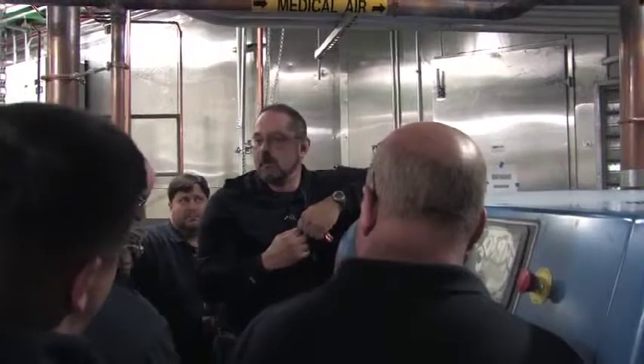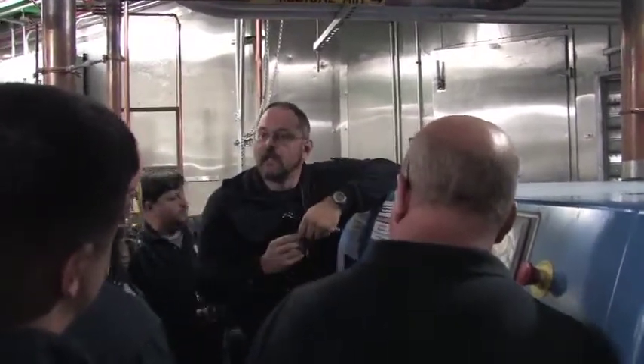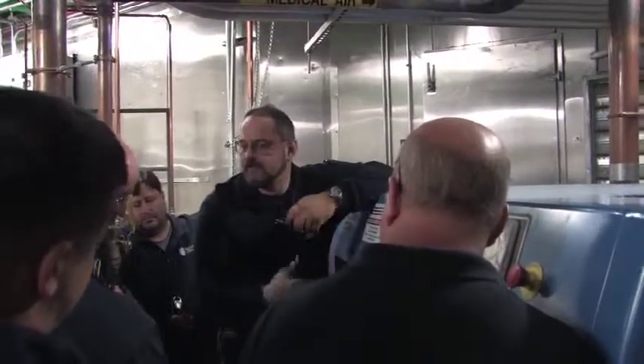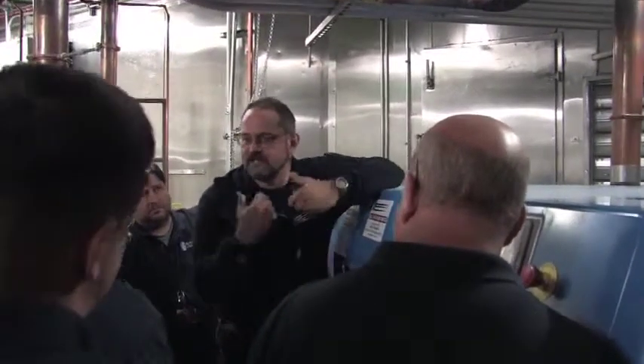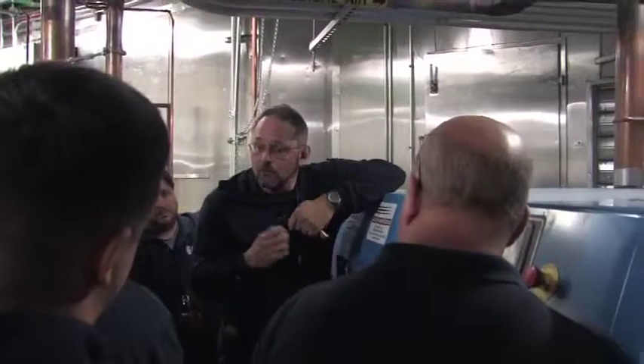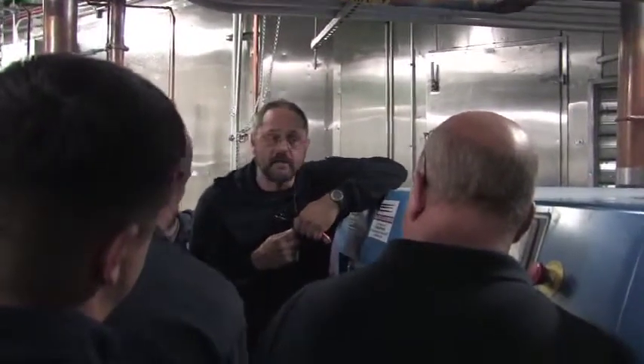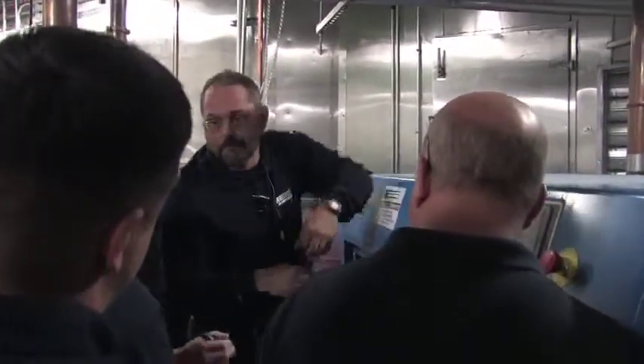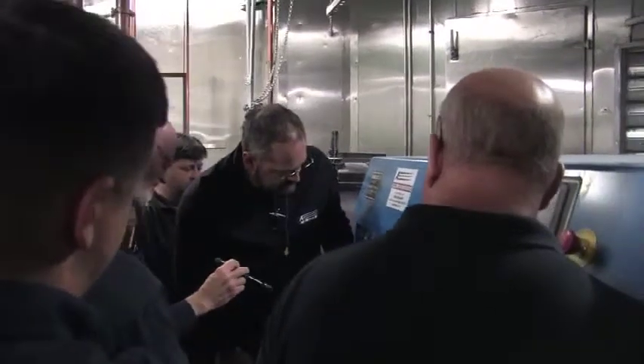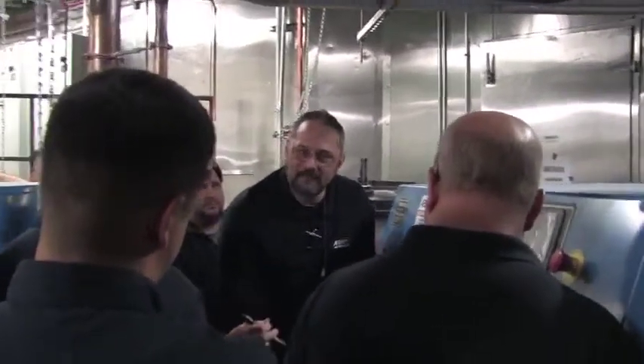And it had a soft starter on it. It was only designed to go forward, but a forward signal to the windings now was a backward signal. And when everything else checked out, they figured, oh, they're all phased the same, we hooked them up the exact same way they were, so we're all right. Those were all nice assumptions, you know, usually, except this time it wasn't. And they did manage to salvage the machine, but, let's put it this way, that one runs about 25 degrees warmer than its sister machines. I'd like to look at all the gauges when that happened.